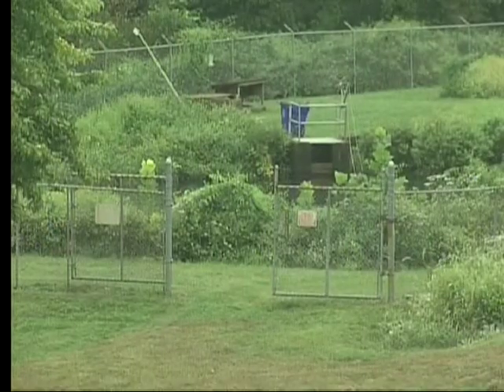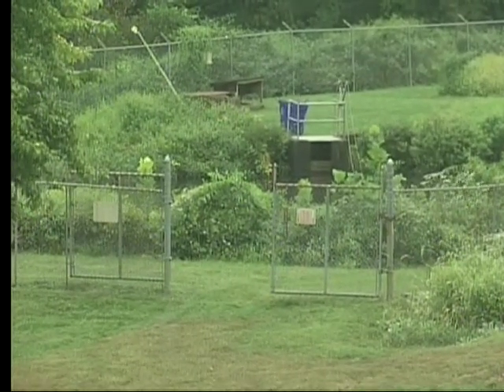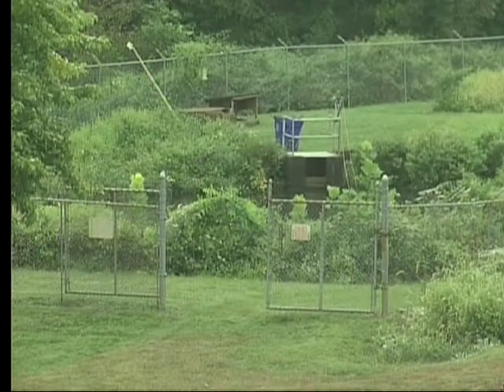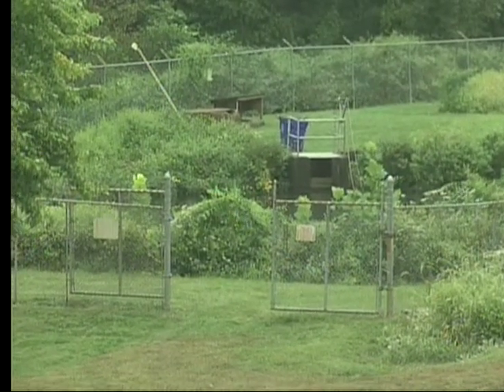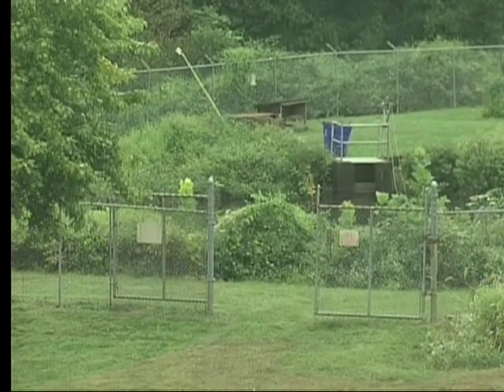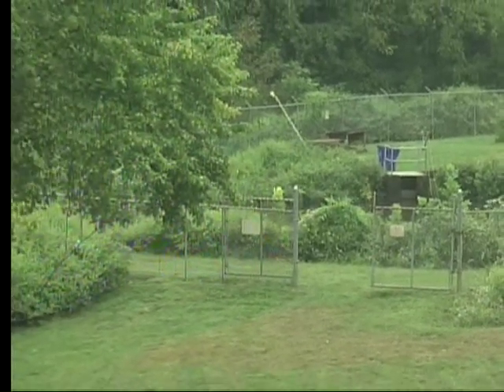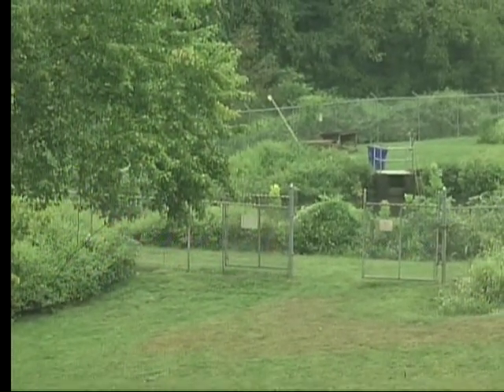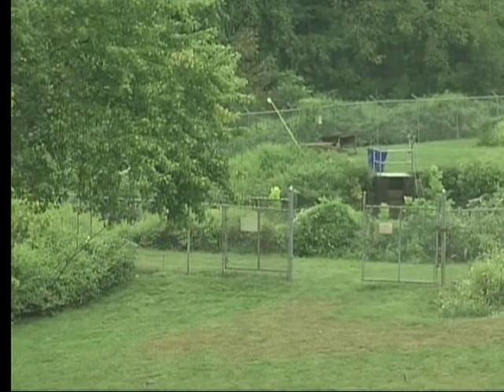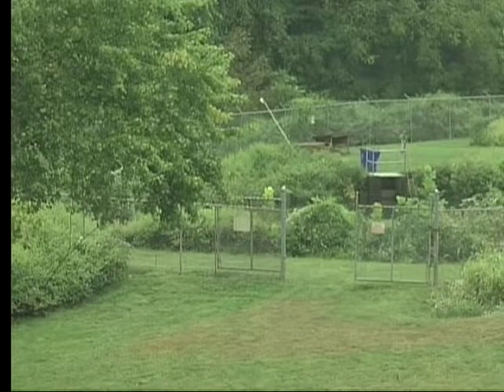Brent, where does the dirty water go? Obviously there's more of a process, so something's being dumped somewhere in the process. Well, as you mentioned, we do produce dirty water. We clean our filters when we backwash them, which removes the dirty particles, the final process before we pump it out of the system. Also, out in the basins, we have that mud, dirt, sludge. We pump that over to the lagoons, where we do treatment.